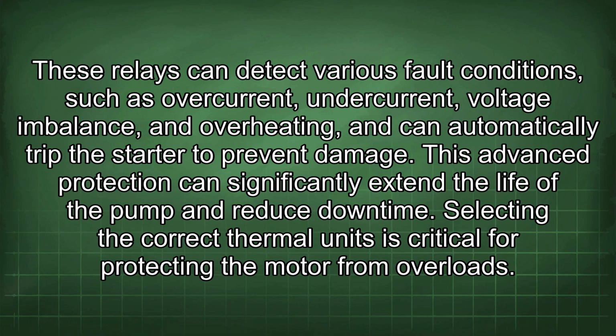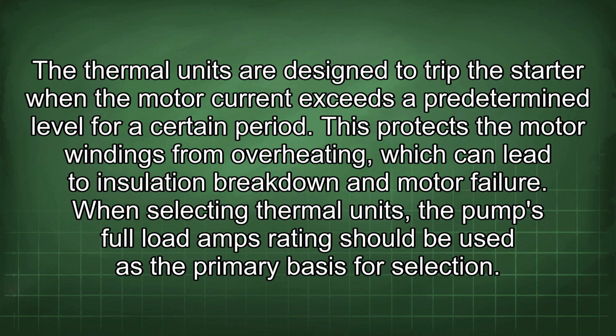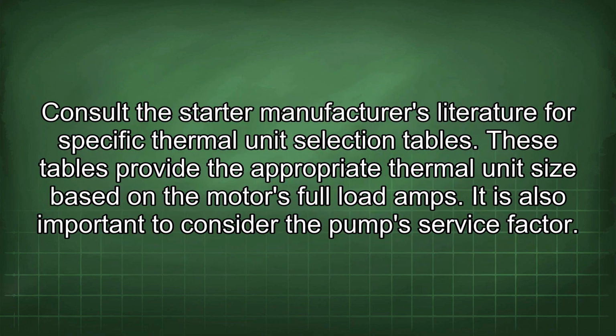Selecting the correct thermal units is critical for protecting the motor from overloads. The thermal units are designed to trip the starter when the motor current exceeds a predetermined level for a certain period. This protects the motor windings from overheating, which can lead to insulation breakdown and motor failure. When selecting thermal units, the pump's full load amps rating should be used as the primary basis for selection. Consult the starter manufacturer's literature for specific thermal unit selection tables. These tables provide the appropriate thermal unit size based on the motor's full load amps.